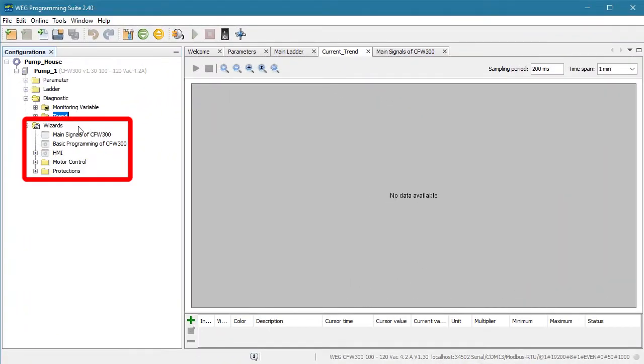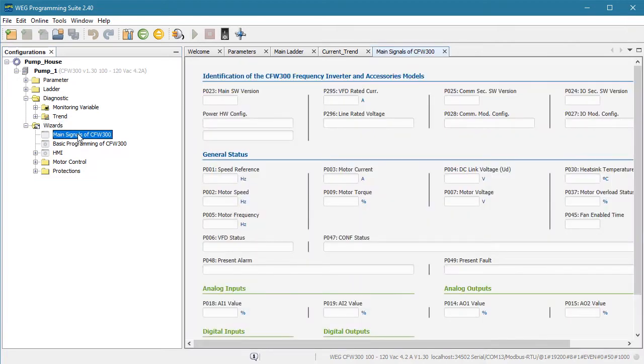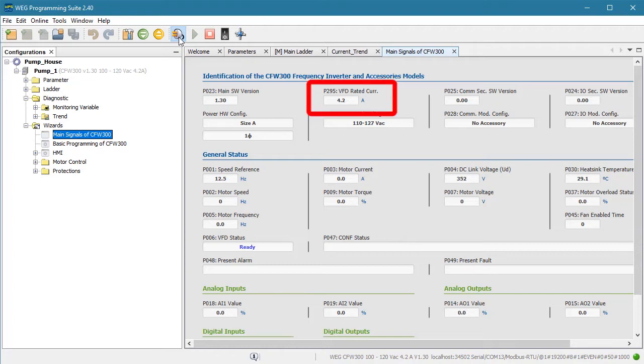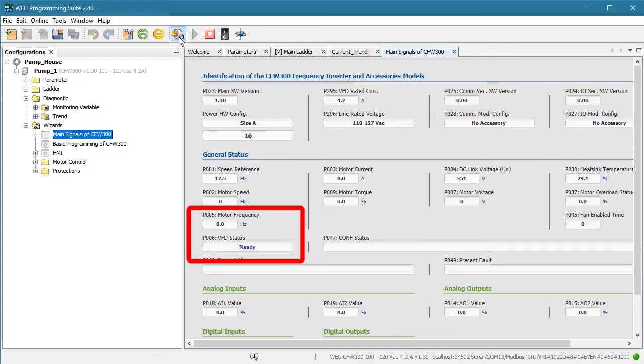They show you all the common things you'll typically want to monitor in a nice clean format that is easy to visualize. For example, it is so much easier to double click on this main signals wizard – of course, I need to be connected to the drive for this to work – and instantly see everything I need to know about the drive in one place without having to remember that I need to look at parameter 295 to see the drive's rated current or parameter 27 to see what kind of I.O. card is installed. For example, if I watch the drive speed and status and reach over and hit the run button, sure enough I see what the drive is currently doing.